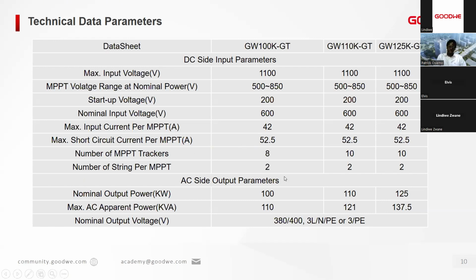Also looking at the AC output side, you can see that the nominal power is the power rating of the inverter, but you can get 10% more on the maximum AC apparent power. This is in case you have oversized on the DC side, which is normally 50%. Therefore, for the 100, you will be able to get 110. For the 110, you will get 121. For the 125 kilowatt, you get 137 kilowatts. Therefore, you are able to get more in case you oversize and the weather conditions are optimal.